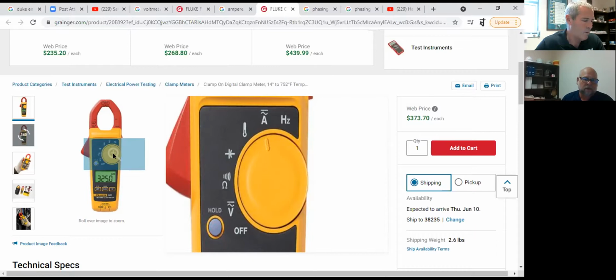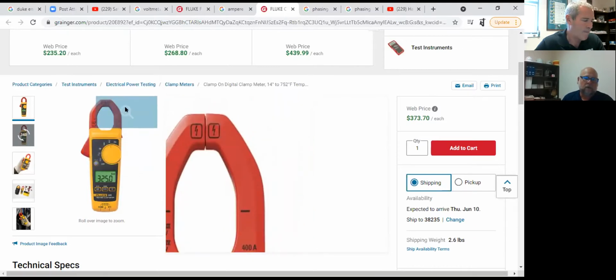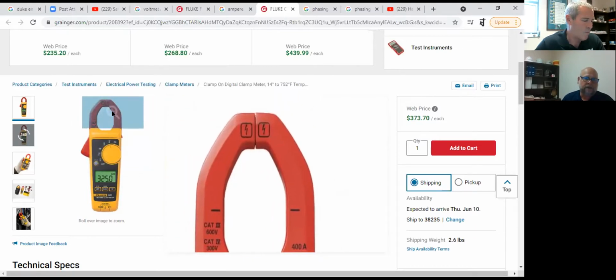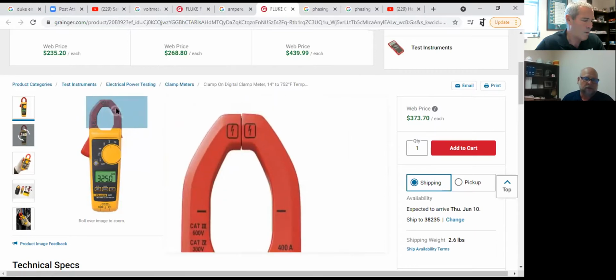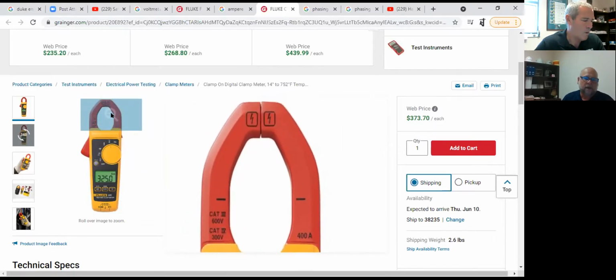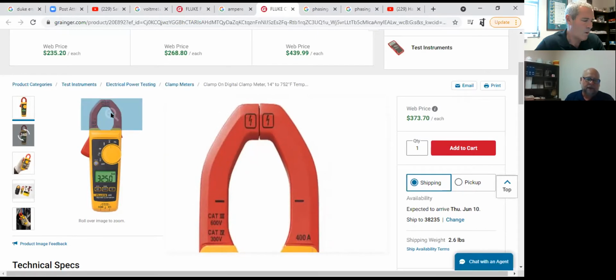But the biggest thing you want to look at here is your amperage. If you're trying to check amps on conductors coming in or out of a transformer, this is very important to remember: you want to check one wire at a time. You do not want to put like a neutral wire and an energized conductor in it together, because it's going to cancel each other out and give you a 0 or near 0 reading. That's very important, that's going to have you scratching your head.